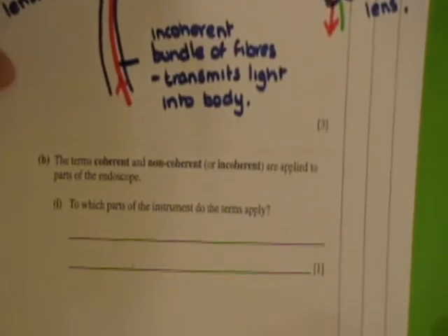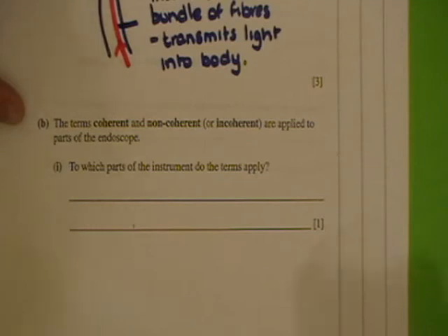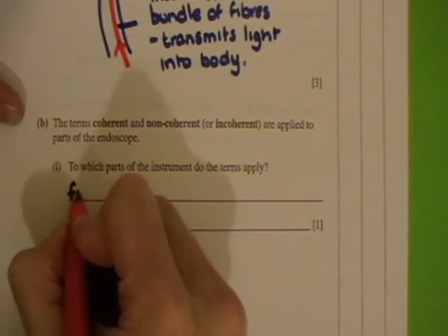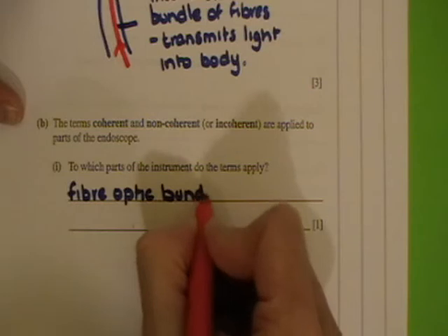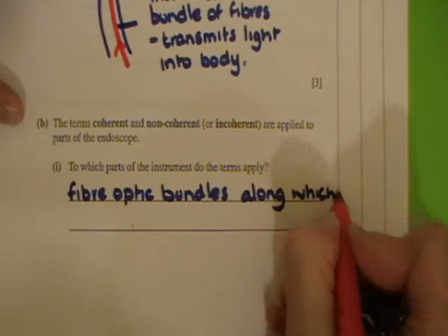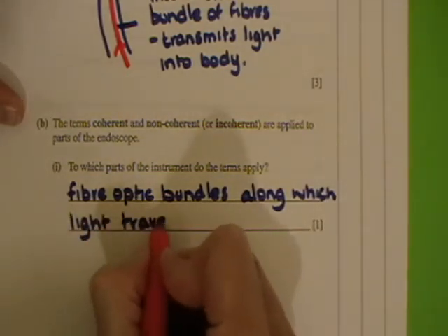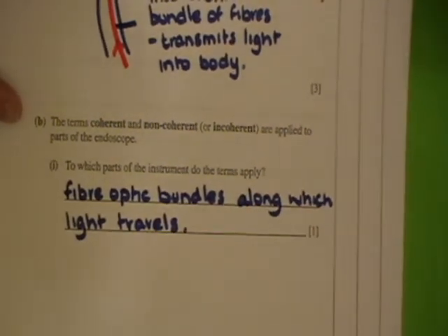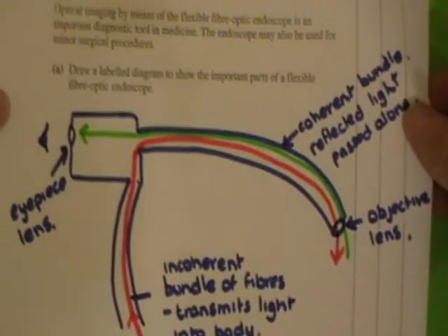Part B of the question: the terms coherent and non-coherent or incoherent are applied to parts of the endoscope. To which parts of the endoscope do the terms apply? They apply to the fiber optic bundles along which light travels — the fiber optic bundles which allow the light to be passed into the body, and then the light to move out of the body again.